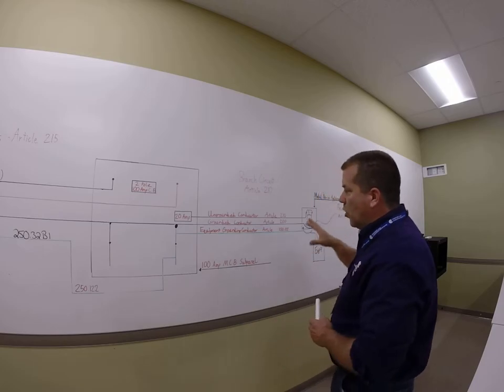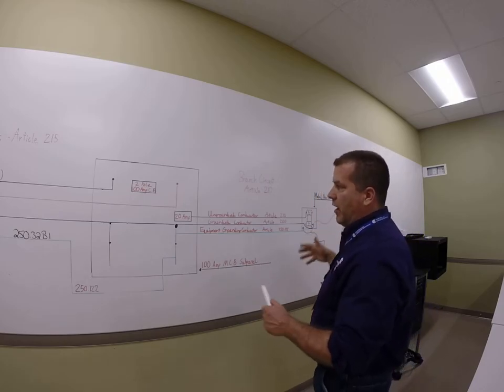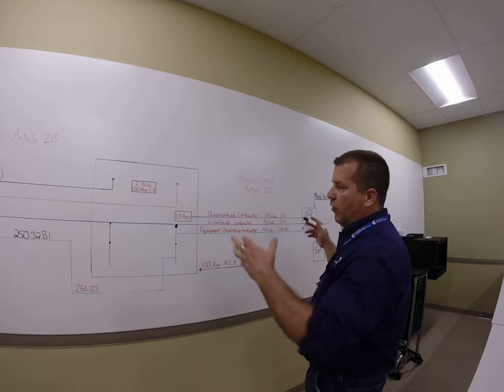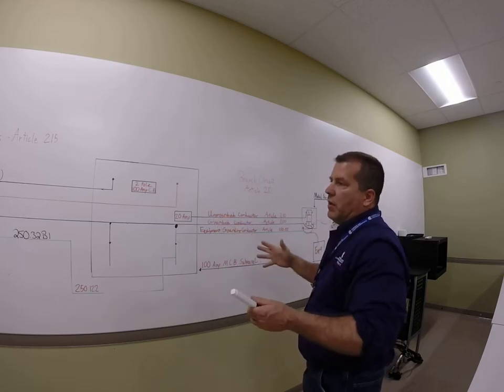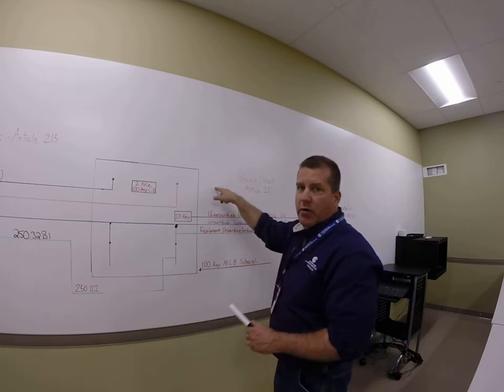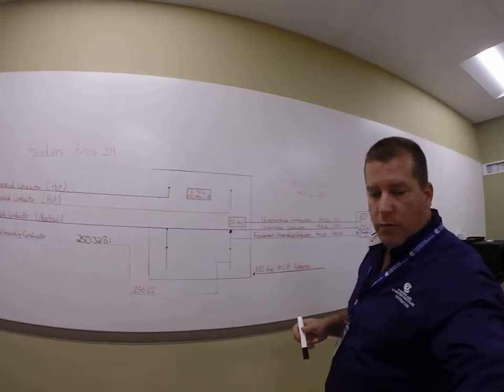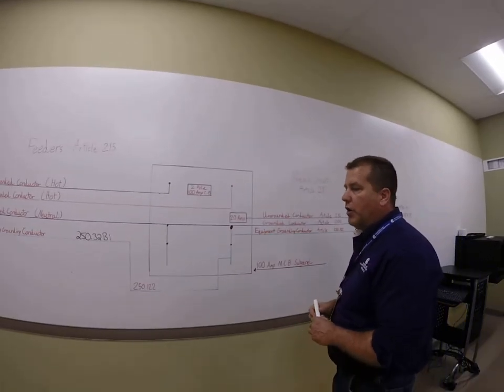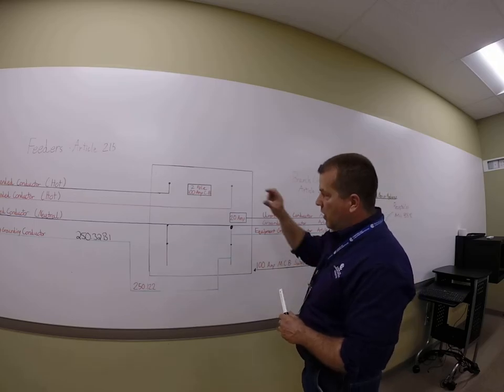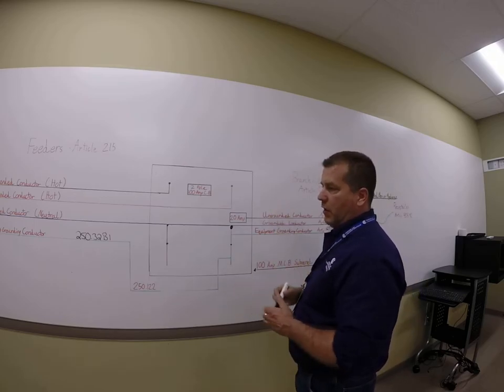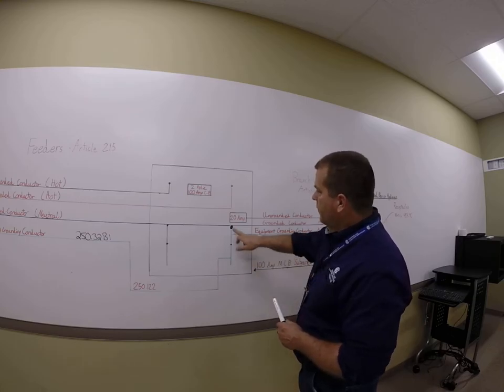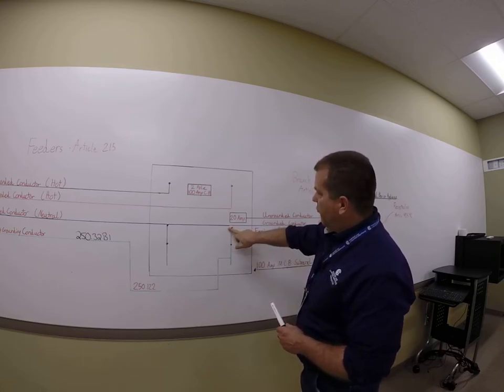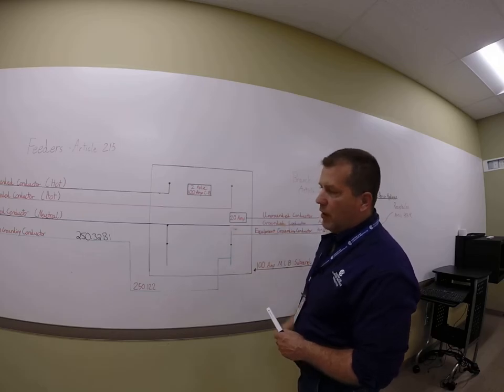There is a lot more to this than that, but the reason I have this drawing up here is that fundamentally we're always installing sub-panels in places. We have to understand that this panel is going to come with that green screw because they don't know if they're going to use it as service equipment. There's a sticker that comes in that box that says for service equipment only, and you put the sticker on the panel because it's service equipment. In this installation, the main bonding jumper shouldn't exist.